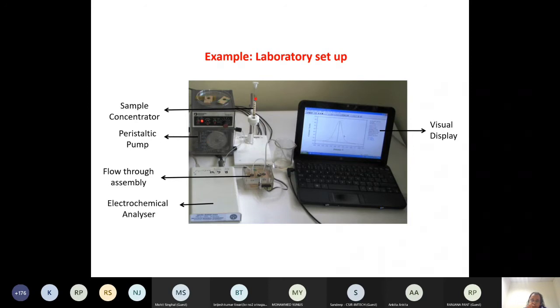The enzyme glucose oxidase is immobilized on the electrode, and the more glucose in the blood, the more the production of current, and that current can be detected by this electrical device. With the software it's possible to see what kind of current is there when we are scanning with the potential. But in the commercial devices, the potential is just kept fixed. It's a static potential, they know at what potential this current is going to appear, and they just measure the current.